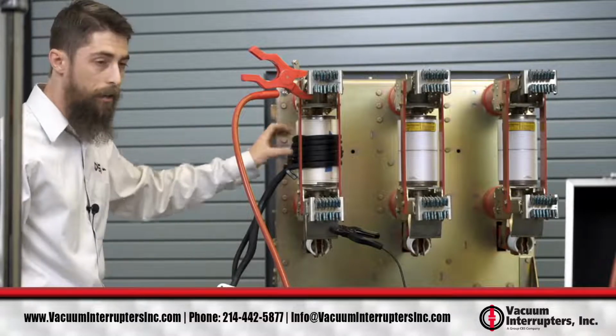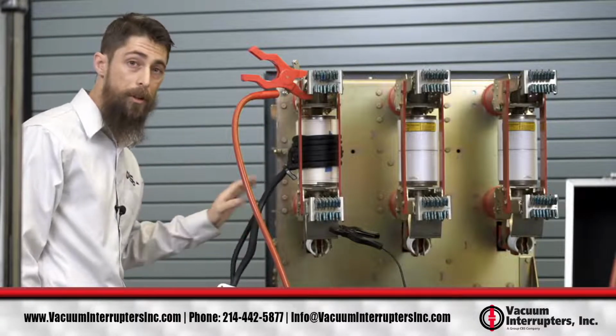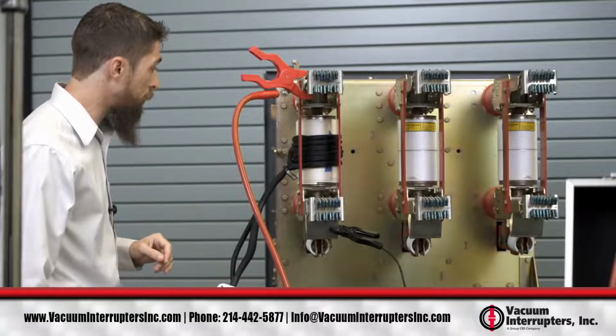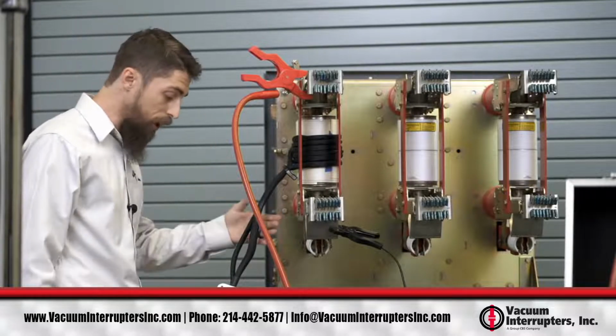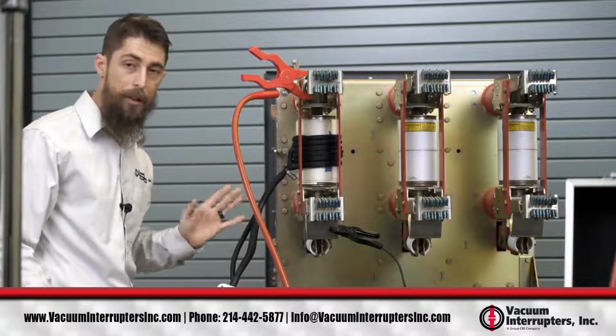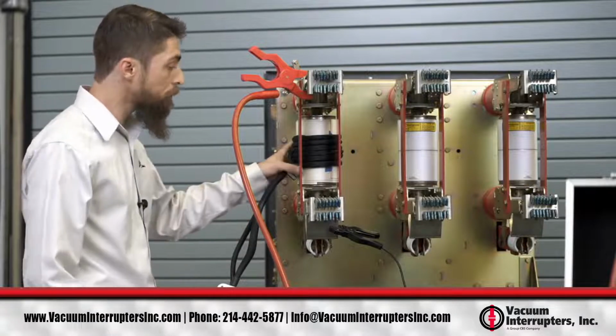We're not sending the high voltage back through our magnetic field coil, so there shouldn't be any damage to the test set. If the high voltage does come back through the magnetic field coil, there is a chance that it could fail.